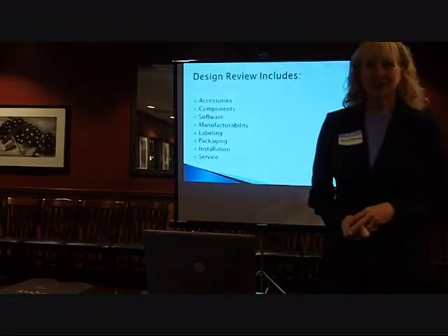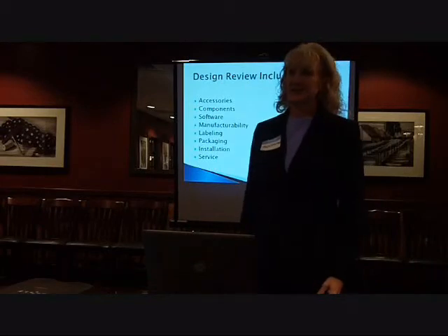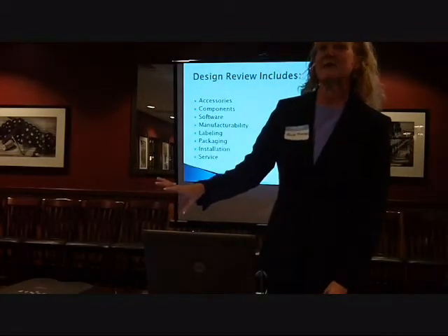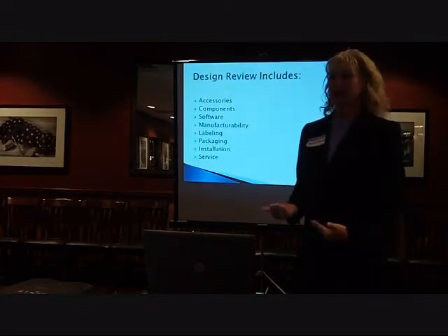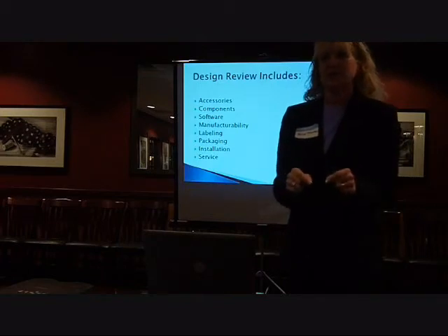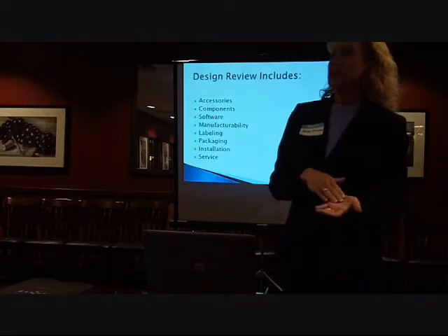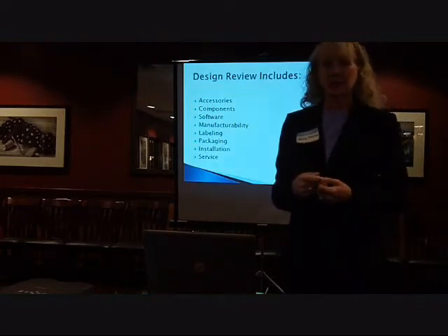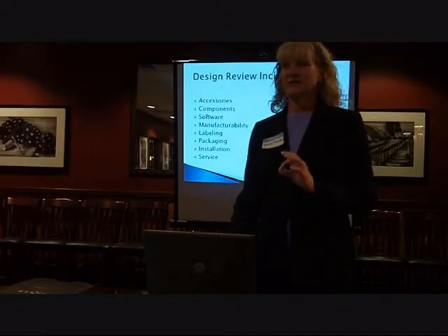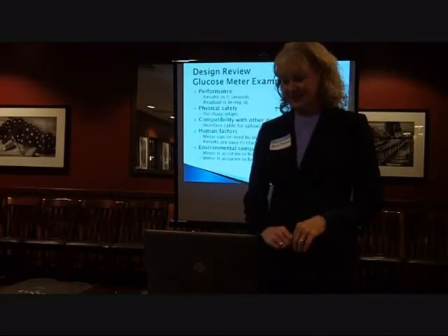It looks at the installation and service, and usually we don't look that far down the line when we're designing something. You're just going to make it, and somebody else is going to take care of that piece of it. So when you're looking at how these things are going to come back, who is actually going to service them, can they even access what they need to service when it comes back? Are there things that the end user can do? Are there filters that can be replaced, or does everything need to come back for maintenance? So it is very, very comprehensive, and in the final design review, that's really where you dot all your I's and cross your T's.